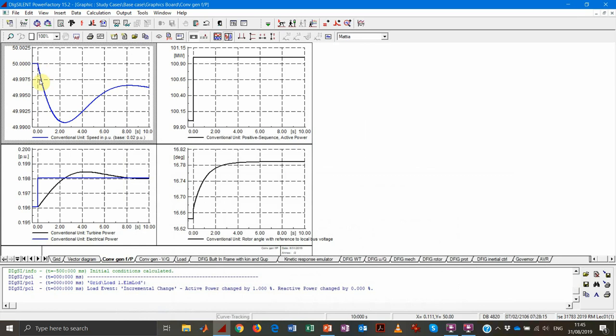The frequency, as expected, is declining because we have an excess of consumption compared to production. At the point where mechanical power matches electrical power again, the frequency stabilizes. We call this point the nadir — the lowest frequency in the dynamic simulation. Afterwards, mechanical power exceeds electrical power, the frequency increases again, and we reach a new steady state: a lower but still stable frequency.